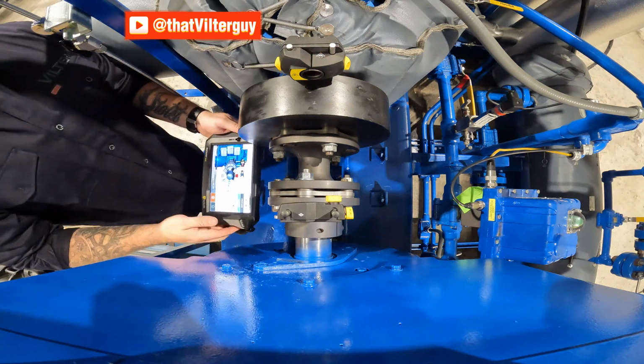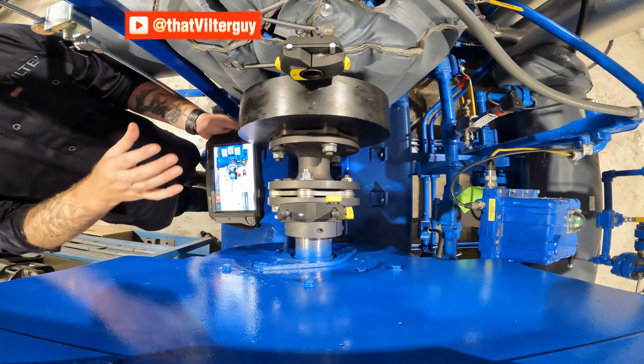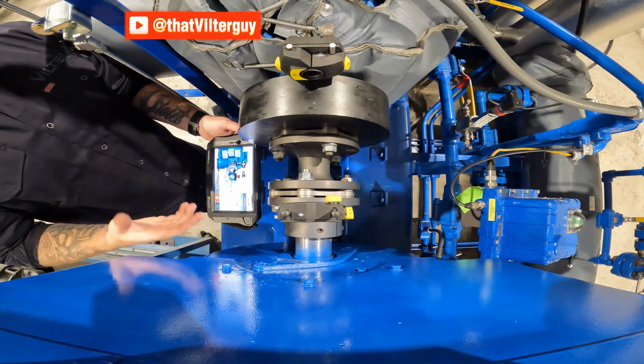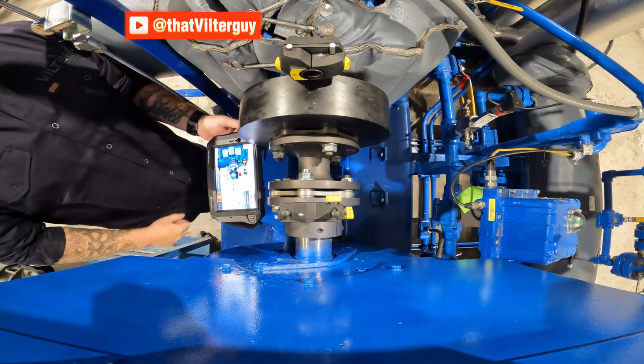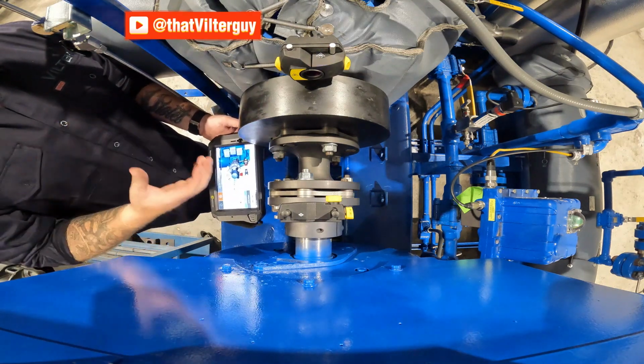So now that we got the laser centered, we're ready to do that first roll. Again, what's really nice is we only have to actually take 3 positions, 3 positions at a minimum. That's all we need for an accurate or relatively accurate number. A 4 position maximum for this device is all it requires. But again, what's really nice is any 4 locations.